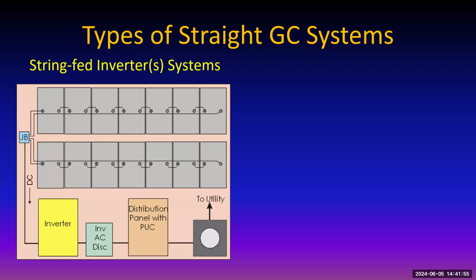And therefore, in order for every module to produce the very same current, every one would have to be the same model that performs exactly identical to the one next to it. That when the sun shines on a certain intensity will produce exactly the same current. But if one of those modules gets shaded, then that one module's not going to want to produce that much current, no matter what you do with it.